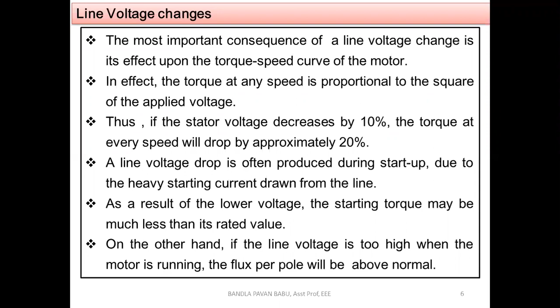On the other hand, if the line voltage is too high when the motor is running, the flux per pole will be above normal. Since T is proportional to V squared, if the voltage is exceeded, the torque also responds twice as strongly. The flux per pole, in the sense the rotating magnetic field created in the stator and linked with the rotor, also exceeds its normal value. So the maximum EMF induced in the rotor, that is E2, also exceeds its normal value. That should not happen.